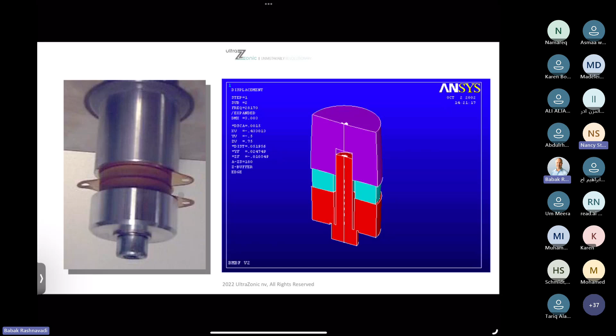Please, next slide. Now, on the left side, you see a stainless steel sink, and on the bottom you can see the two transducers in just a small ultrasonic equipment. What I want to show here is that the stainless steel quality has to be a very flexible stainless steel, so that we are assured that the wave the transducer is creating is really transmitted 100% in the water. Otherwise, if your stainless steel is too stiff or too hard, you will immediately have maybe 20 or 25% less cavitation in your water.